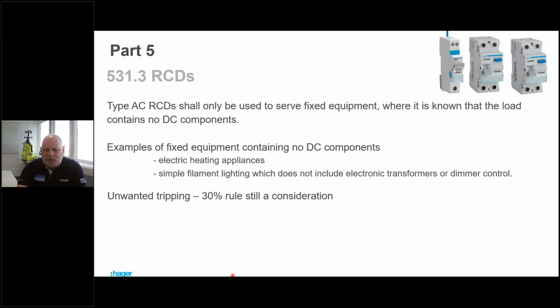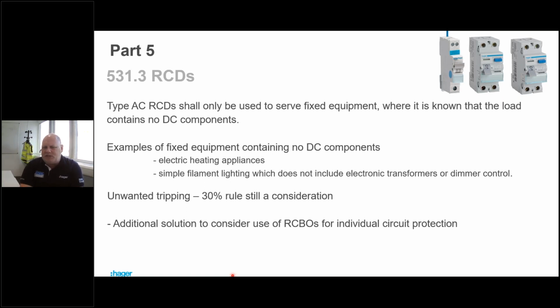Okay, people still use split load boards. They are migrating slightly towards a main switch and RCBOs. And this is what they're saying now. Additional solution would be to consider the use of RCBOs for individual circuit protection. Okay, 9 milliamps is not a lot of earth leakage, and that's your 30%.